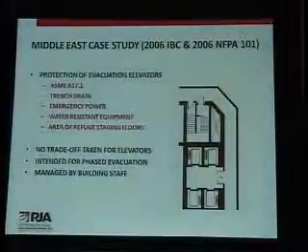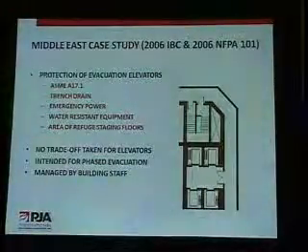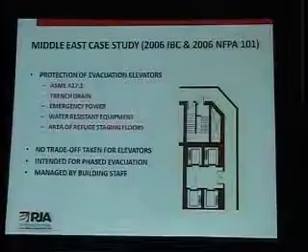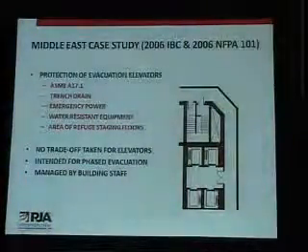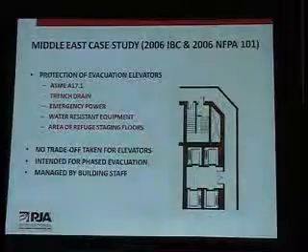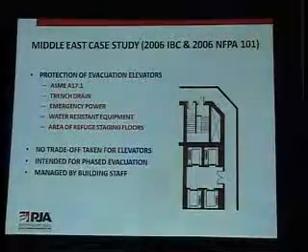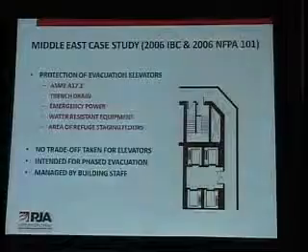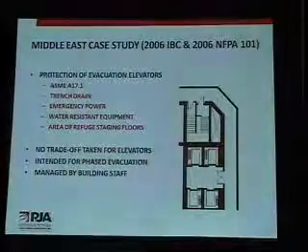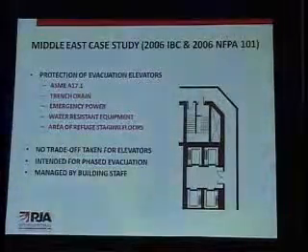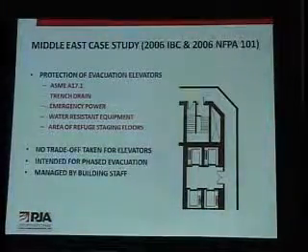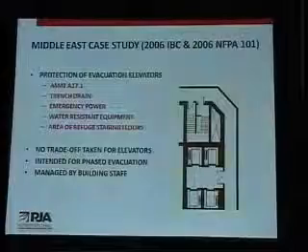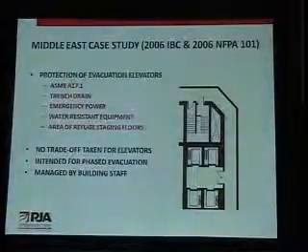You can see the stair has 2 doors, one door entering the area of refuge and the other door then proceeding down the stairs. So occupants are encouraged to identify the area of refuge as being a place where they can rest and wait instead of continuing down the stairs, freeing up the stairs for other occupants who are capable of proceeding down. Or they can come around and queue for the lifts that are then directly accessible from the elevators.